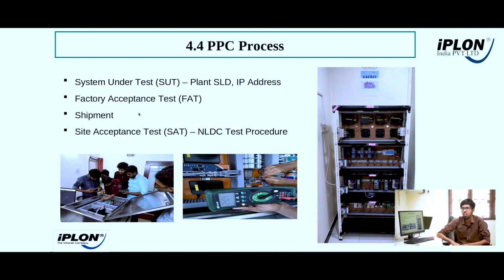After that, our engineer comes to the site. We test whether all those controls are working fine or not. We test as per the draft NLDC test procedures. In August, NLDC released the draft test procedure. As per the test procedures, we have to conduct the tests for active power, reactive power, all those controls. We test and submit the results. We have implemented this process in nearly 6 sites, around 700 megawatts. So it's working efficiently and well. Thank you.